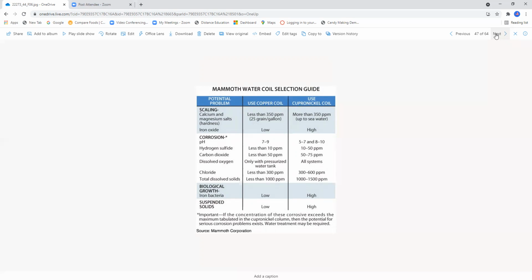On the lower left-hand side of the page, it's figure 44.6, selection guide for determining whether a copper or cupronickel heat exchanger should be used. Based on your water contamination, you will choose either copper or cupronickel. Cupronickel has a higher resistance to corrosion all the way up to seawater, whereas copper does not. So if you want the better material, cupronickel is the way to go by far. Now, is cupronickel cheap? The answer is no. You will pay for it, trust me.